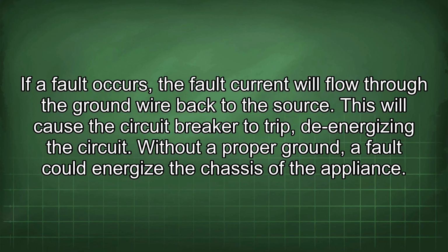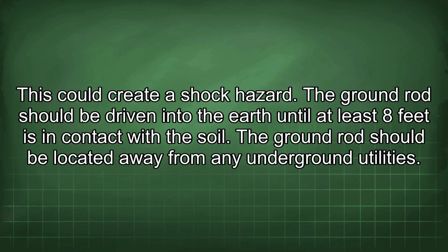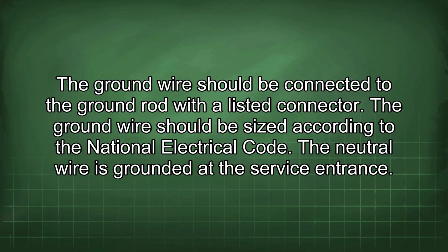If a fault occurs, the fault current will flow through the ground wire back to the source. This will cause the circuit breaker to trip, de-energizing the circuit. Without a proper ground, a fault could energize the chassis of the appliance. This could create a shock hazard. The ground rod should be driven into the earth until at least 8 feet is in contact with the soil. The ground rod should be located away from any underground utilities. The ground wire should be connected to the ground rod with a listed connector. The ground wire should be sized according to the National Electrical Code.